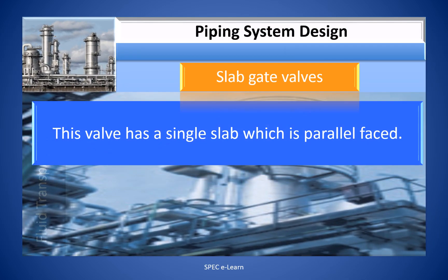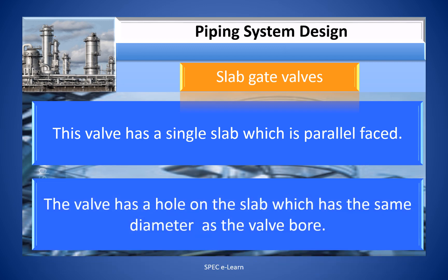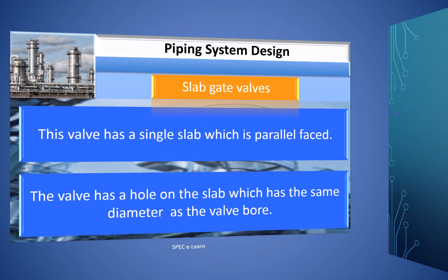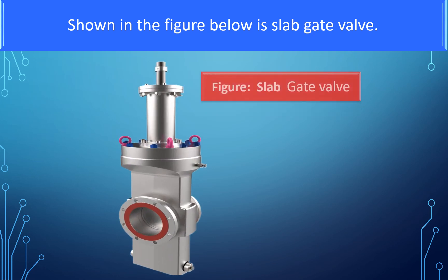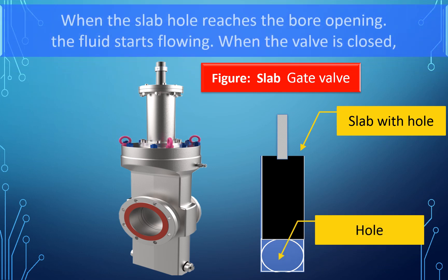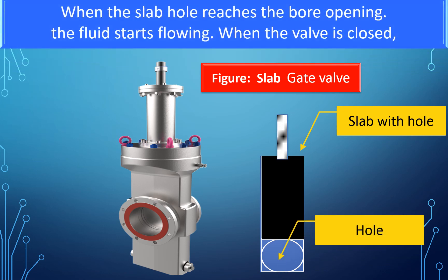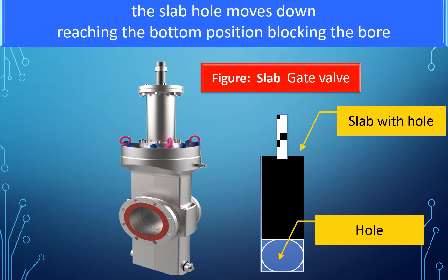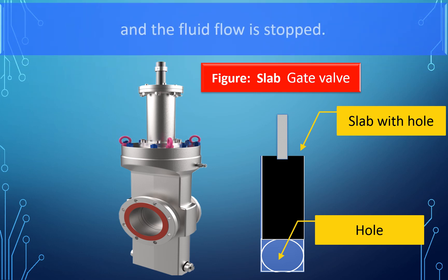The slab gate valve has a single slab which is parallel-faced. The valve has a hole on the slab which has the same diameter as the valve bore. As the valve is opened, the slab gate moves up from the closed position. When the slab hole reaches the bore opening, the fluid starts flowing. When the valve is closed, the slab hole moves down, reaching the bottom position and blocking the bore, stopping the flow.